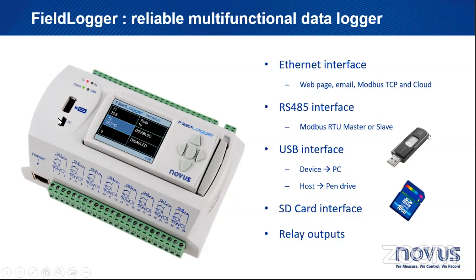USB interface, two, one for PC configuration. So Bruno, I want to configure my FieldLogger. What do I need? You only need a USB type B cable. That's it. Oh, but should I buy a special cable from you? No, it's a USB type B cable, simple one, okay? Very simple one. And here, the host, which is useful if you want to collect data using a USB stick. So you just plug the USB stick in and your data automatically backs up on the USB stick, okay? On the back of this HMI as well, there is an SD card interface where you can plug your external memory expansion. And you have those relay outputs that I mentioned before.